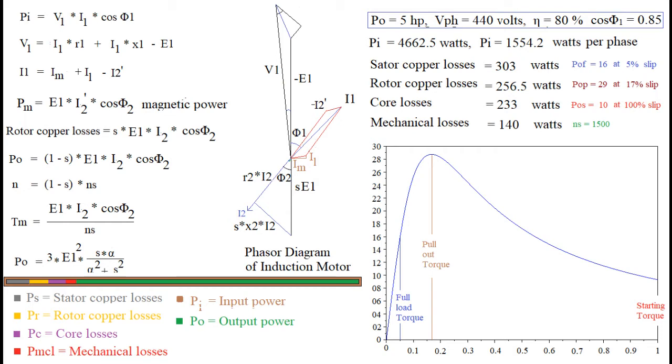First is a magnetizing component of no load current Im, second is a loss component of no load current IL, and last component is a rotor current referred to stator side, that is I2 dash. Product of these three components that account for losses are stator copper losses and core losses. The important product component, that is power transferred from stator to rotor in the form of magnetic energy, is Pm. We have considered same equation in our previous lecture as a P0. Reasons shall be clear in our discussion.